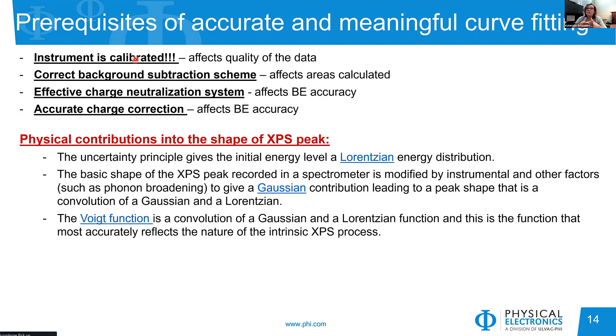Let's look at the physical contributions to the shape of the XPS peak. People skeptical of XPS curve fitting point out that you can put any number of peaks of any shape and get a really good chi-square. But we have lots of physical information about how the spectrum is generated. The uncertainty principle gives us a Lorentzian energy distribution. Instrumental parameters of spectrometer broadening contribute a Gaussian shape. The overall shape of our photoemission peak is a convolution of Gaussian and Lorentzian — a Voigt function is the best mathematical representation, though in practice we use a Gaussian-Lorentzian mix.